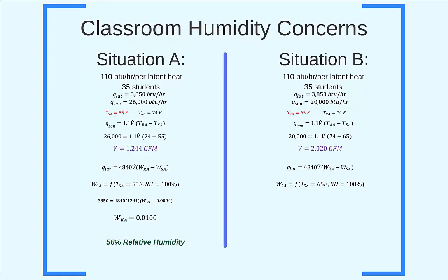Solving the latent equation for the space, we find the humidity ratio for the room would settle around 0.0137 pounds mass water per pounds mass air. Putting that in layman's terms, that corresponds to a relative humidity of 75% at 74 degrees Fahrenheit. Such a humidity level can be distracting to anyone, especially to students trying to learn.